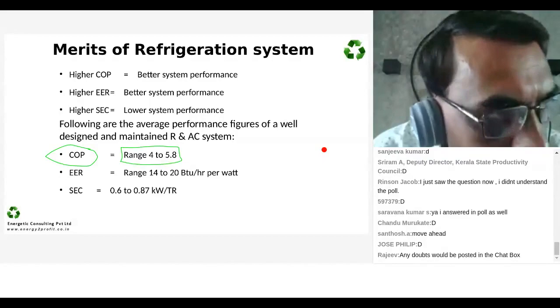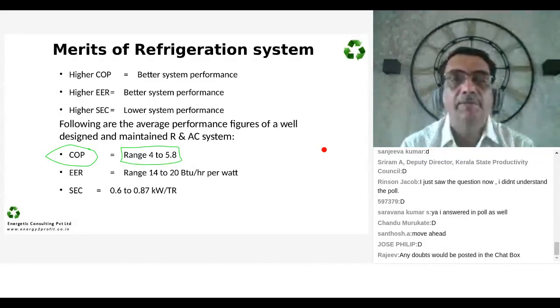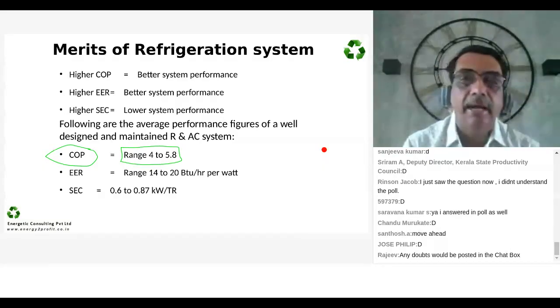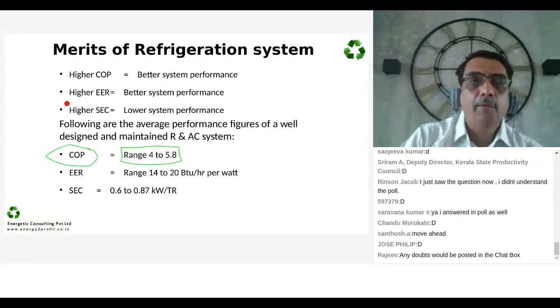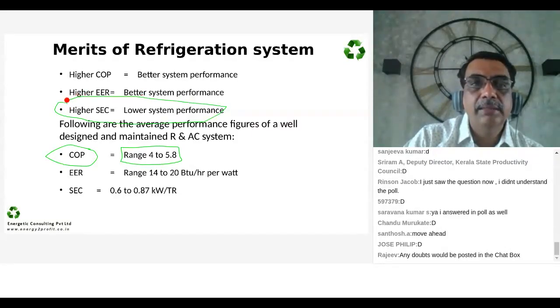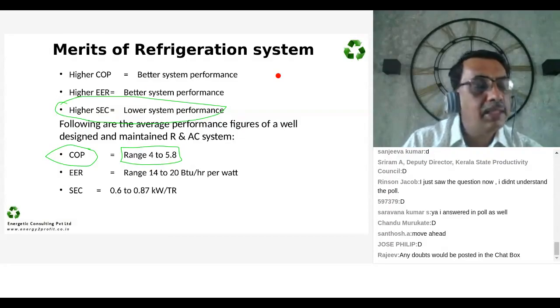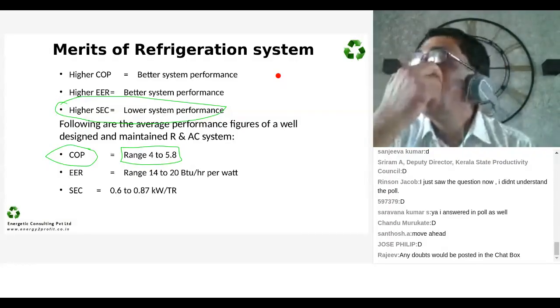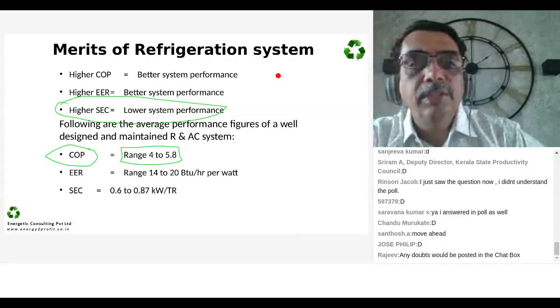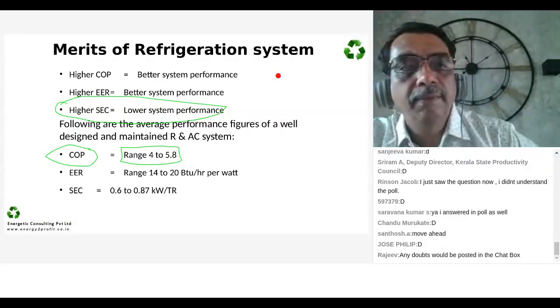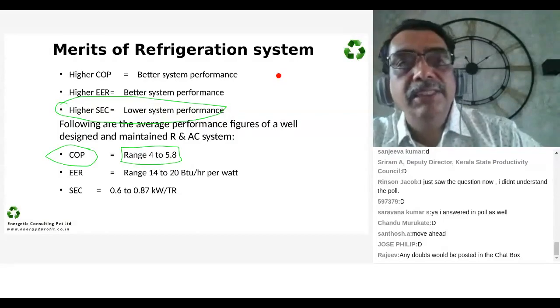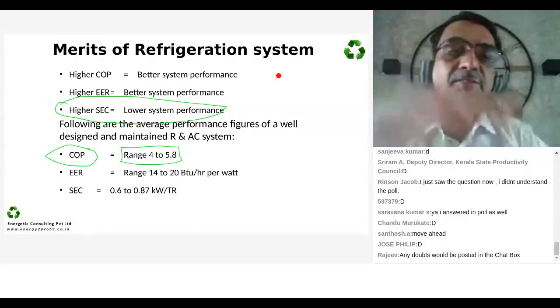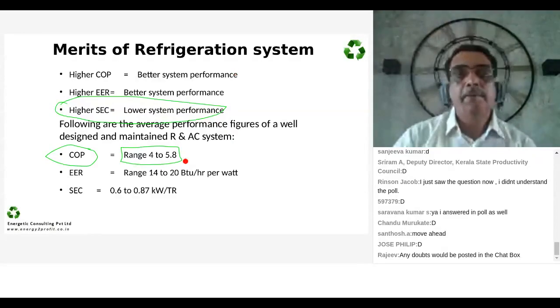And most popularly used is specific energy consumption, where we say kilowatt per TR. What does it mean? How much energy is consumed per TR or per cooling effect. Now you may notice, and I want you to register this, when you are consuming higher energy to deliver 1 kilowatt of output, your system performance is poor. Therefore, the higher the energy efficiency ratio, the better is the system, whereas with high specific energy consumption, the performance is poor.